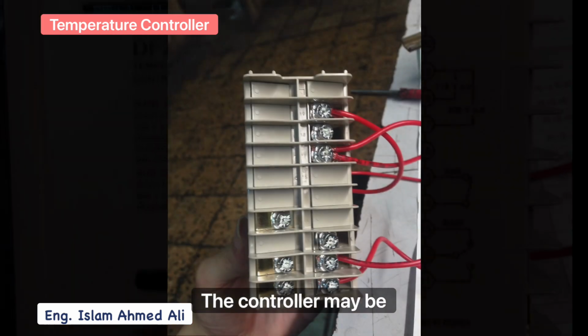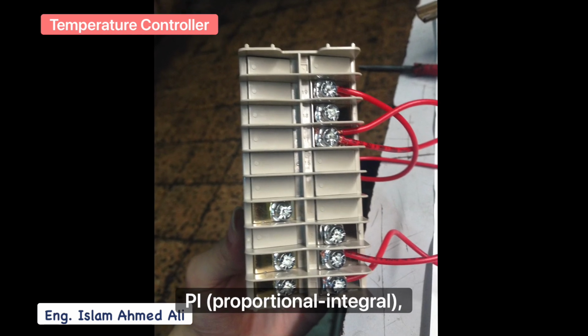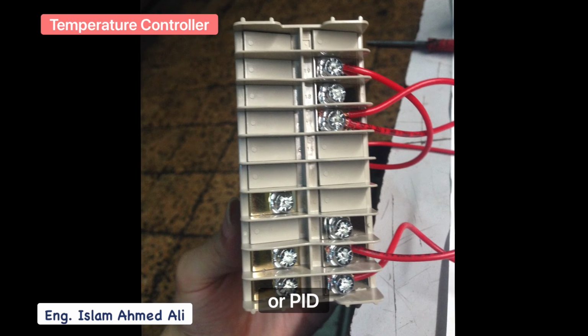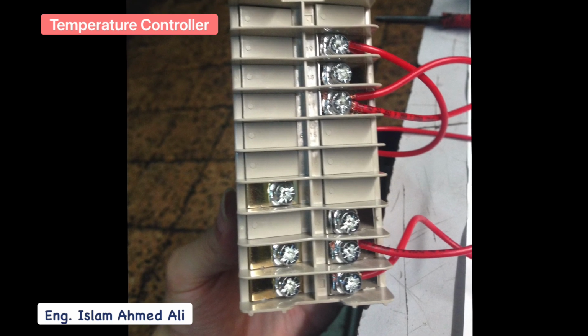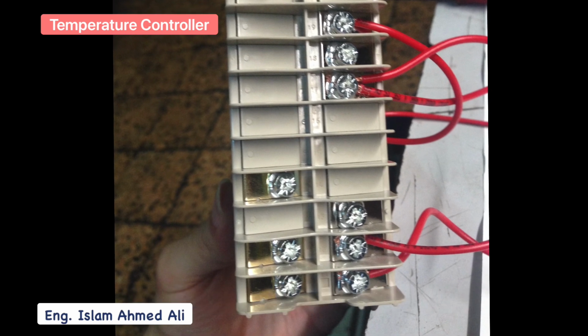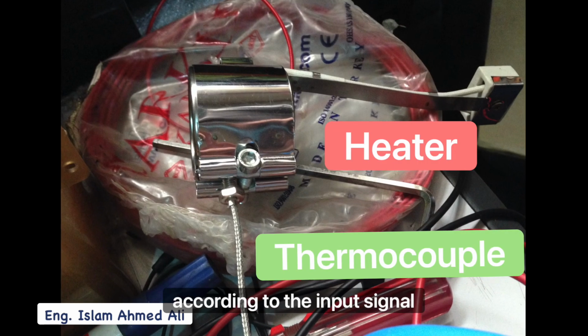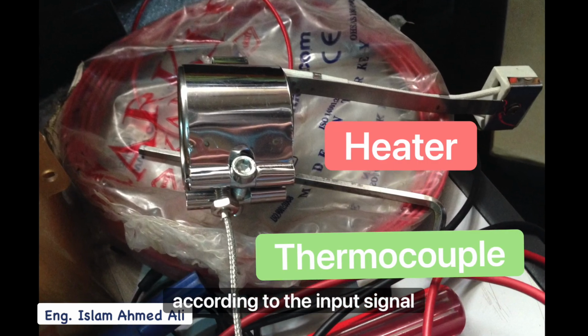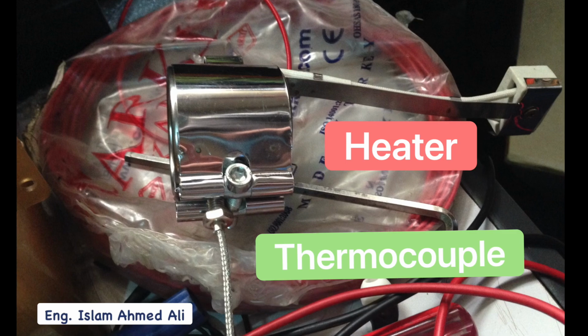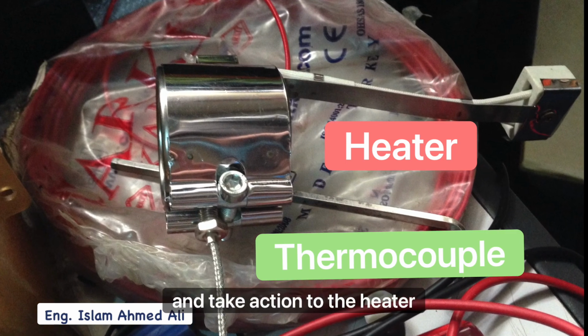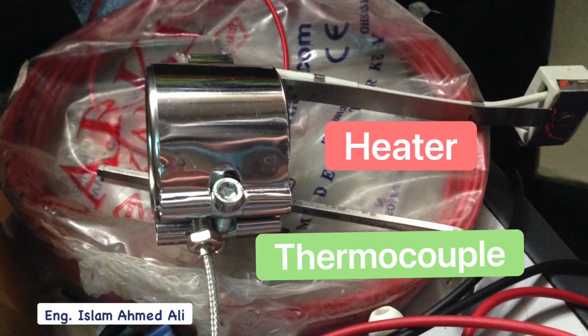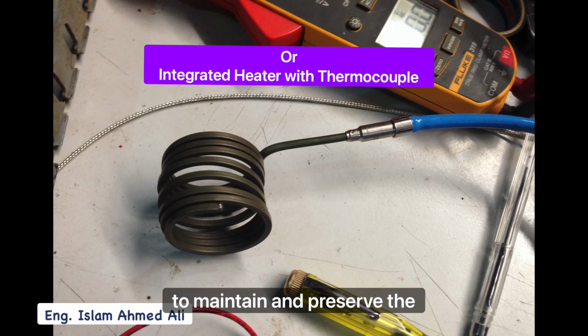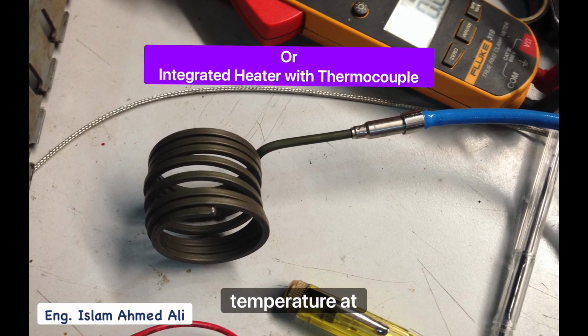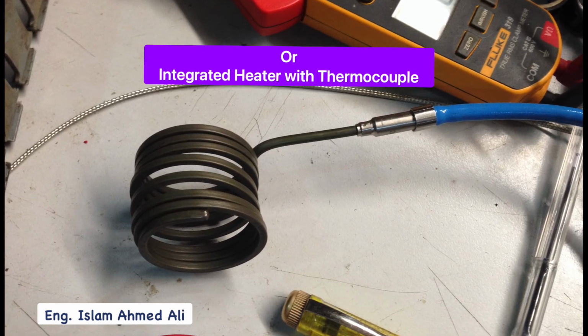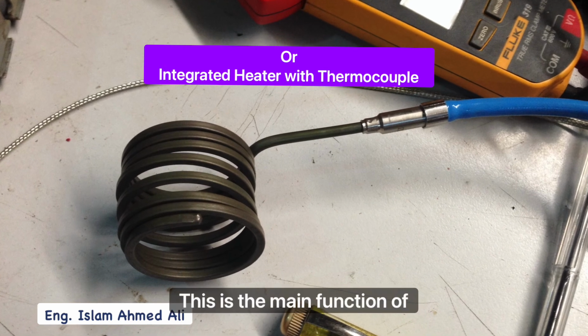The controller may be P (proportional), PI (proportional integral), or PID (proportional integral derivative) controller, which controls the temperature according to the input signal from thermocouple and takes action to the heater to maintain and preserve the temperature at the particular set point. This is the main function of it.